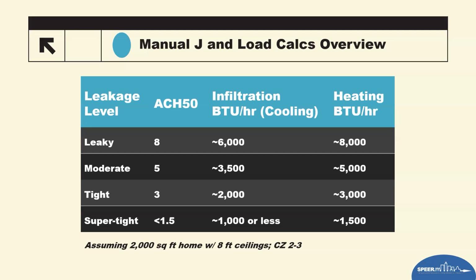So now not only will that house have a much higher result, it could technically still pass due to the ACH being low enough to pass the requirement for the climate zone. But that's now going to allow humid air to become trapped inside the home's thermal boundary. And of course, that also will cause a cascade of problems that cannot be solved without sealing the hole through the envelope. And without testing it and verifying it, you will never know until it's a homeowner complaint.